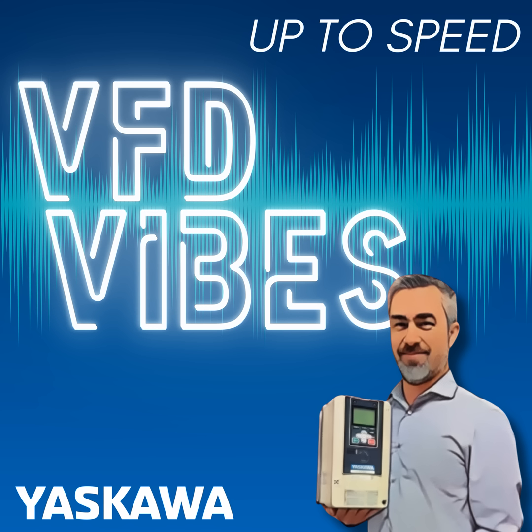And I thought, well, that's interesting. And so I made a sales visit. And this was a particularly interesting visit because this pump station had run for years. And then in the previous fall had been upgraded, and it ran throughout the winter. And this happened right about April. And I'm surveying the facility and noticed there was a large amount of electric heating installed. And I asked if the heating had just been shut off, and the customer said yes. Well, to get to the close of this story, the facility always had a harmonics issue.